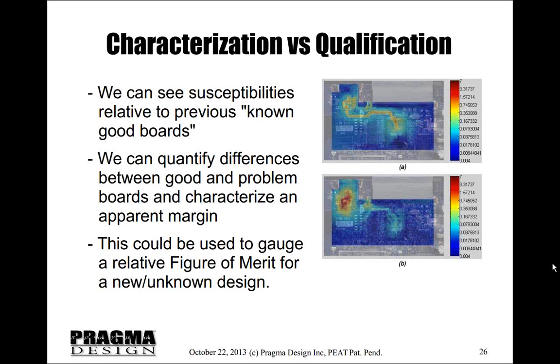But if you've only got one or two parts, you need to do a very low level scan first with very wide steps - a very large matrix - so that if you're doing 100 points, that means you're going to do 100 zaps, and it has to withstand that the whole time. So you want to minimize that until you know what the problem areas are, and then just focus on that.